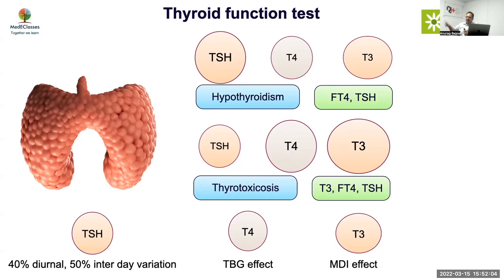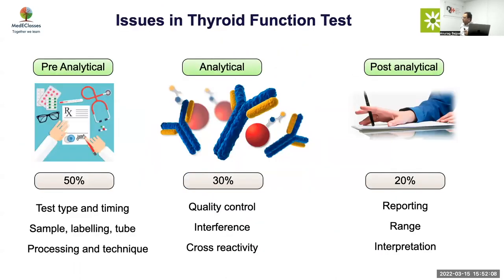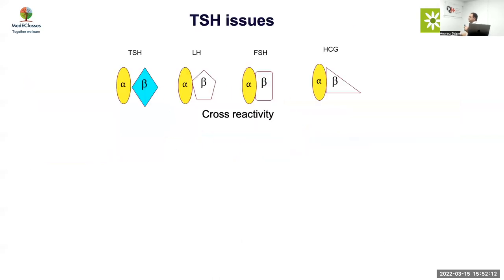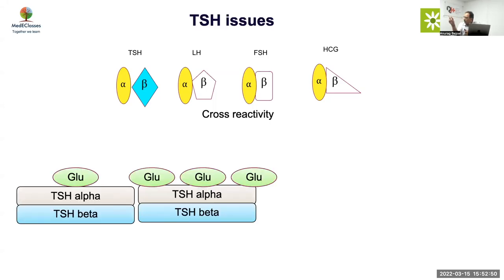Moving to analytical issues — what can be the problems with TSH assays? Cross-reactivity means structurally similar things can be measured. Sensitivity is how low you can measure; specificity is how well you differentiate between two analytes. Earlier assays had cross-reactivity problems, but modern assays don't usually cross-react with hCG as TSH, so that's less of an issue. The second major issue involves differences between TSH isoforms and how immunoassays measure them.